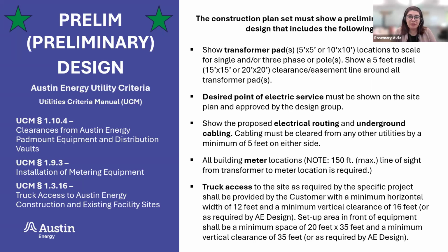We need all building meter locations shown, and that's for us to look at to verify that you're meeting line of sight. Line of sight is basically I'm standing at the disconnect and another person standing at the meter. Are they within 150 feet of each other? And can they see each other? This is for safety. They need to be able to talk to each other. Think two people out in the field. That's the best way to describe meters.